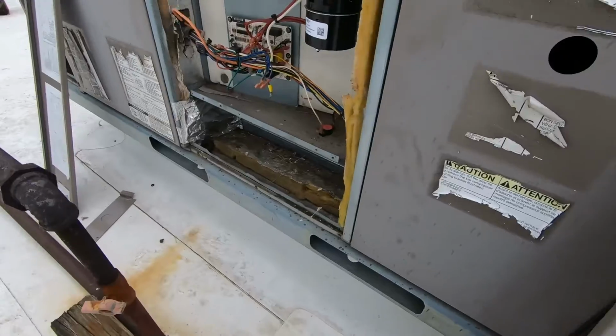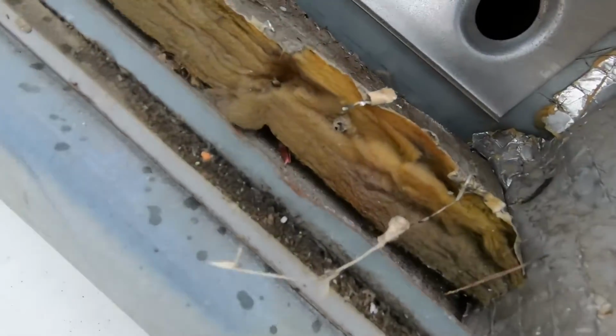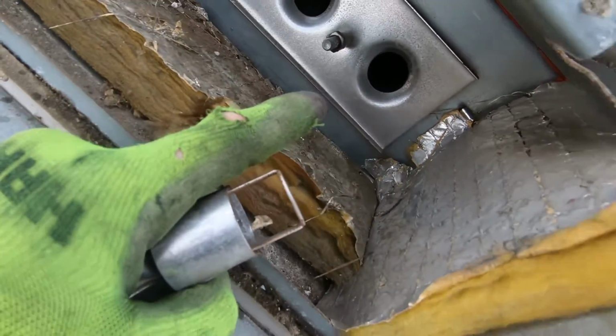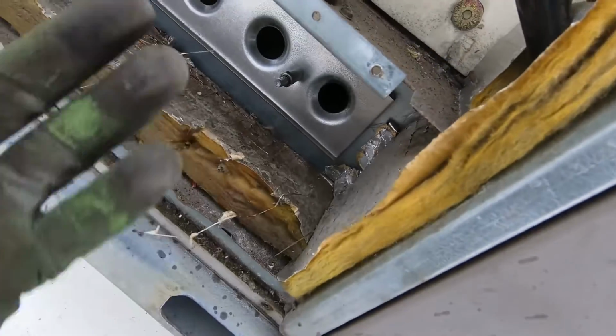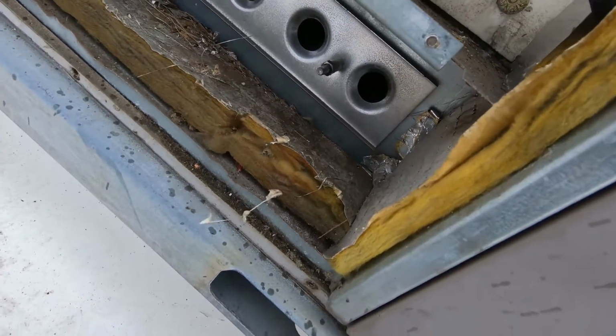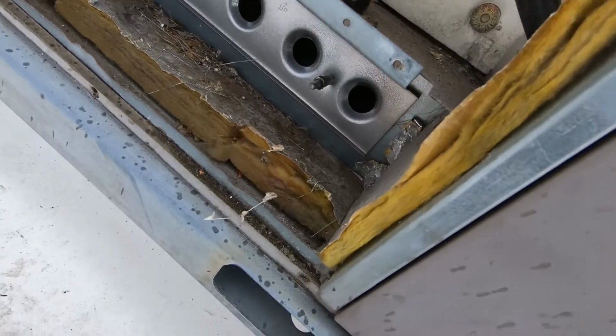Another thing that would cause that to roll out is if there was a crack in this section of the heat exchanger, and when that blower kicks on it, it can disrupt that flame and it will roll out just exactly like you saw here.